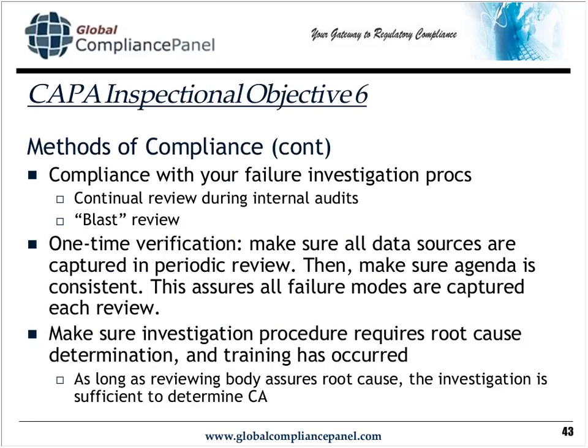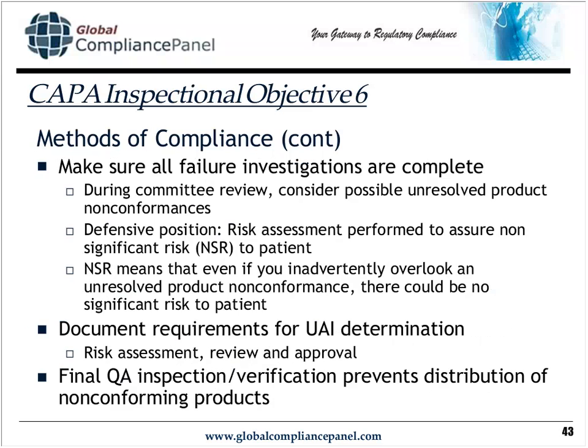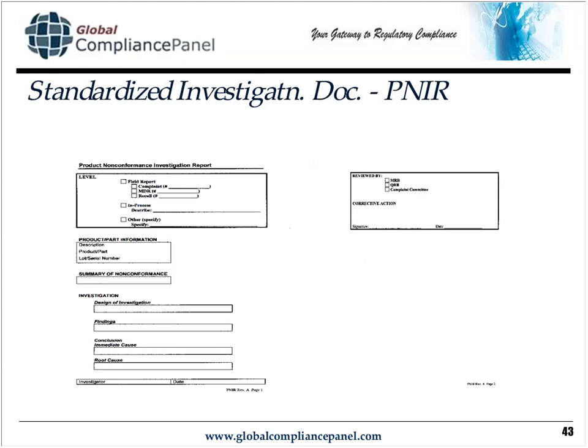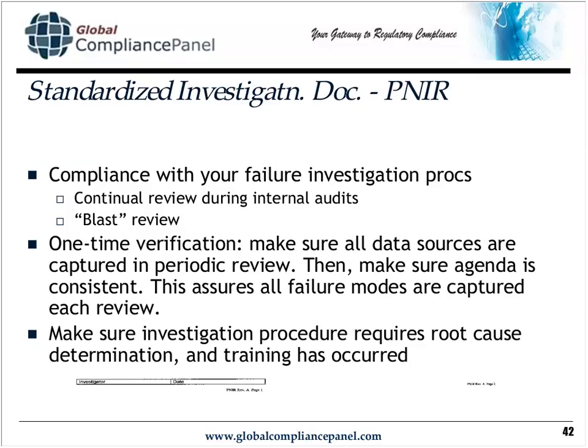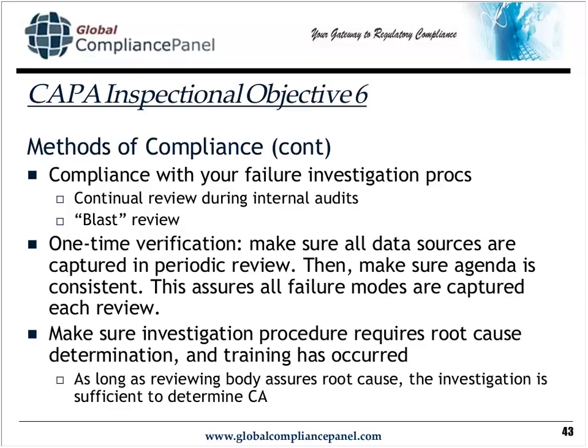We want to make sure that, to be able to comply with this, you comply with your own failure investigation procedures. This form I showed you a moment ago, the PNIR, is a great subject of a blast review, a blitz review, if you will. I've seen it called two different things. I've seen it called blitz reviews here in the States and blast reviews from Englishmen I know who are from our previous notified body. Not sure why that is.